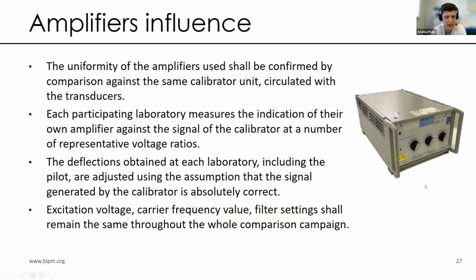As mentioned, also the amplifier has an influence, so we have to assure that the amplifier is stable in time at different pilot and participant laboratories. So usually a calibrator, which is considered stable in time, is circulated together with the transfer transducer. Each laboratory usually uses its own amplifier, and this is regularly checked against this calibrator. So the amplifier is checked at different voltage ratios, and the corrections are made based on the performance of the amplifier.